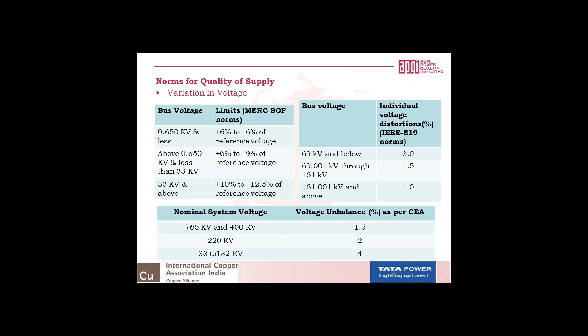The harmonic distortion in the supply voltage permitted as per IEEE norms is 5% for 69 kV and below. Between 69 kV and 161 kV, it is 2.5%, and above 161 kV, it is 1.5%. For the THD norms recommended by CEA for a 765 kV system, the harmonic distortion permitted is 1.5%, and for a typical harmonic of any particular frequency, it is permitted only 1%, whereas THD can be 1.5%.